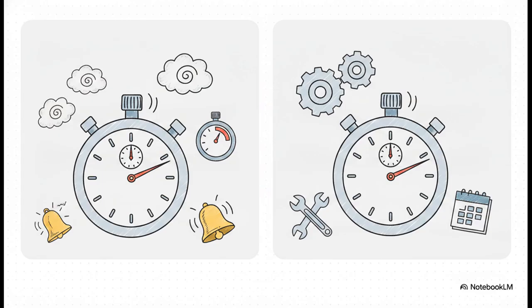Then you have the mechanical operating gear overhauls. These have inflexible, hard limits. You have to overhaul the gear after 5,000 operations or every 5 years, regardless of how little it's been used, or after a maximum number of short-circuit breakings. Whichever of those three hits first, boom, you pull the breaker for overhaul.